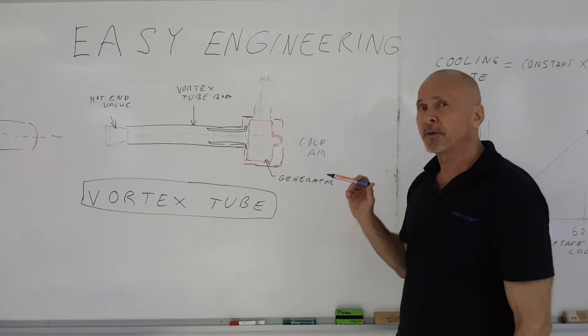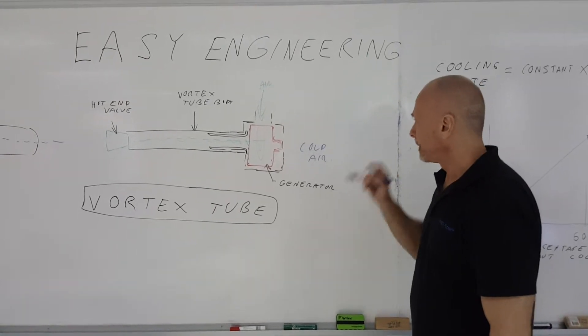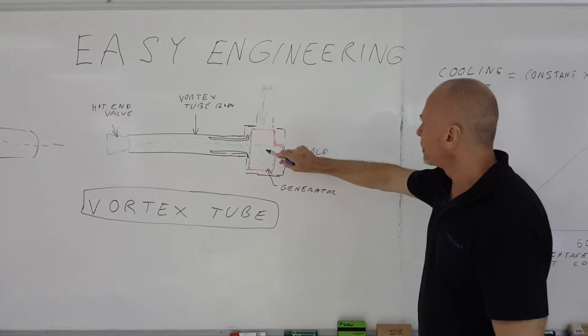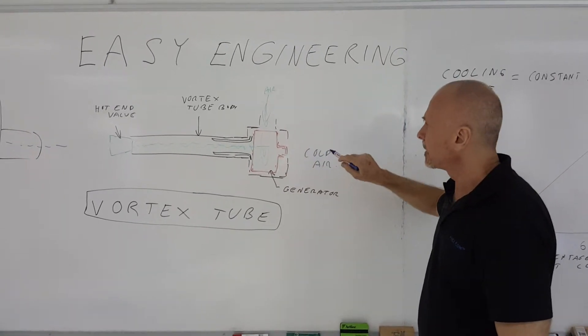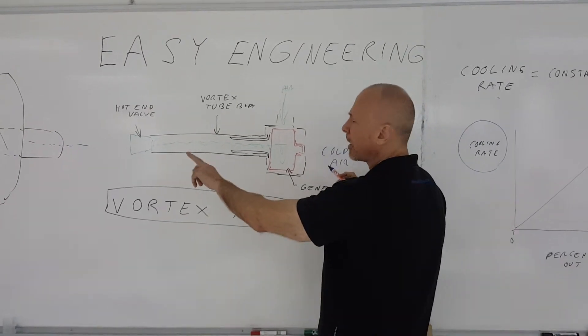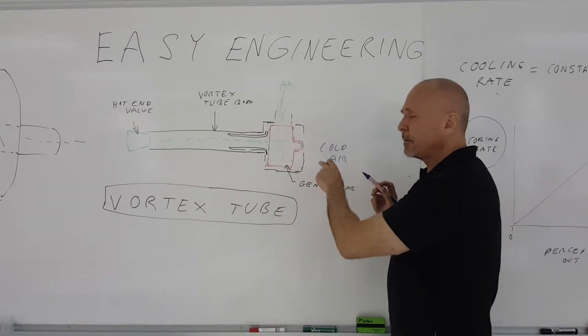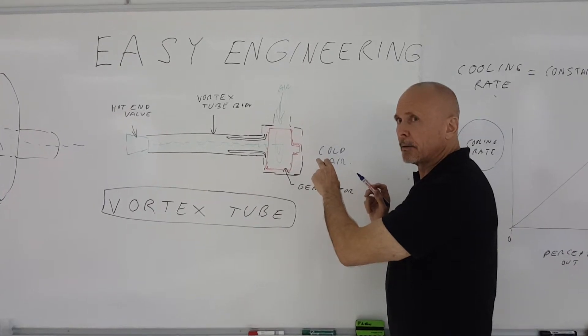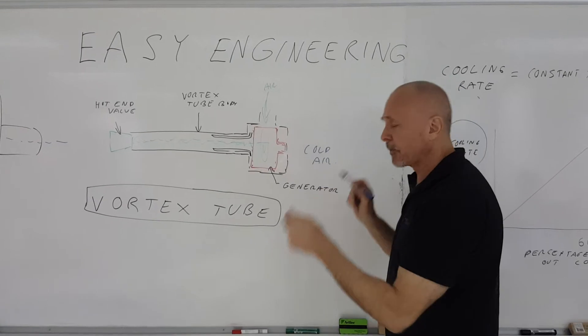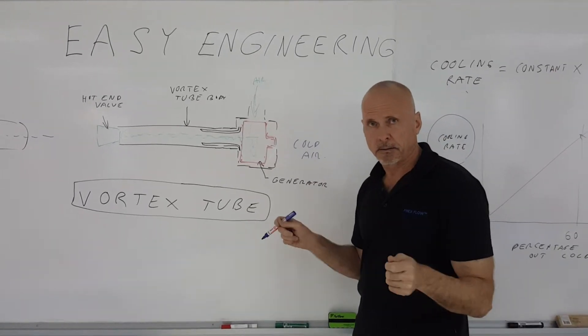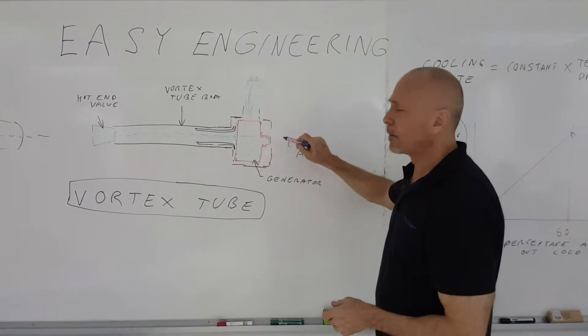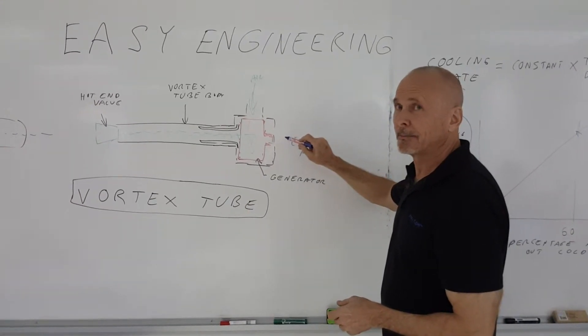Now, the funny thing about the Vortex Tube is that if I want to reduce the temperature at the cold end, I actually have to reduce the flow coming out. If I have more air at the hot end, the temperature at the cold end will get lower. So what happens with the Vortex Tube is that the flow rate and the temperature are interdependent. The higher the flow rate, the less cold the temperature is.